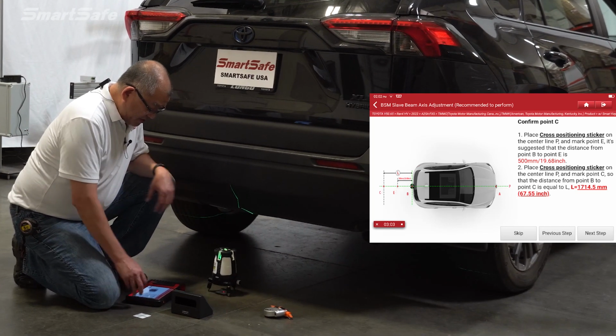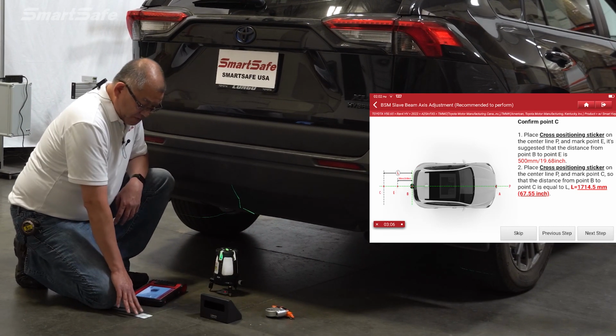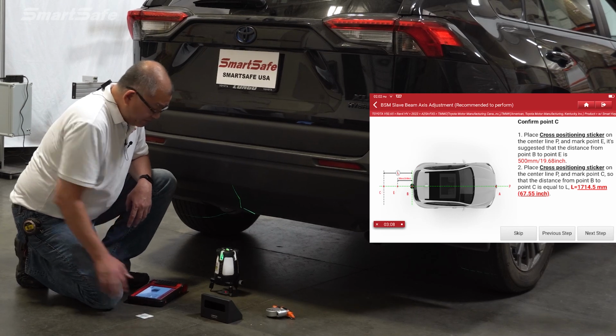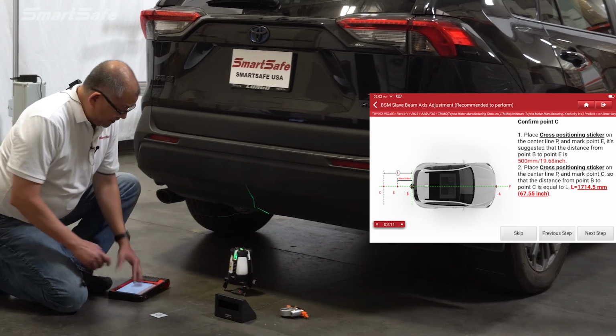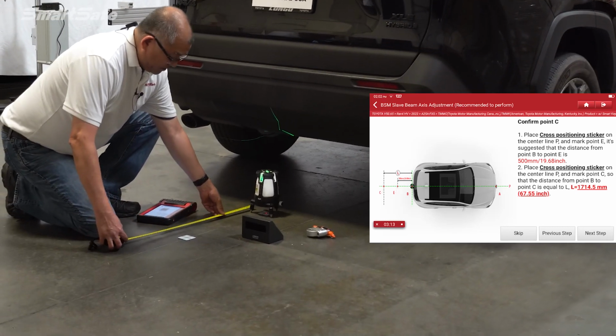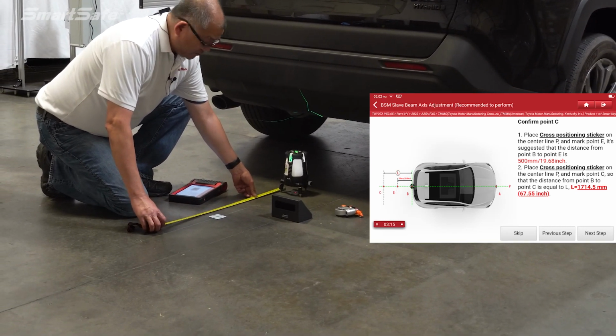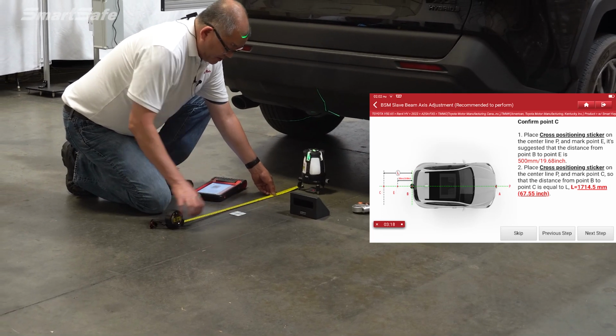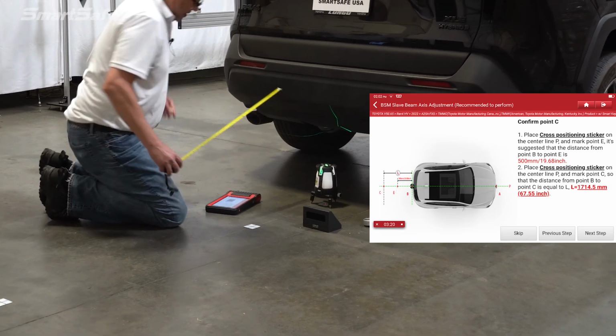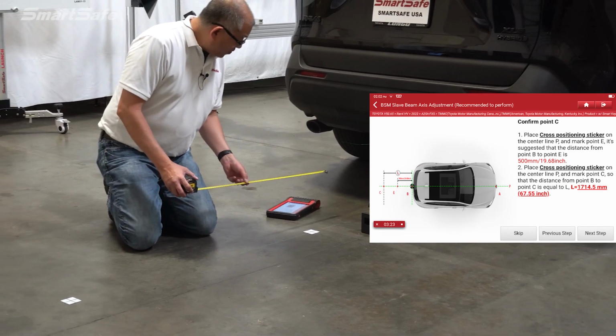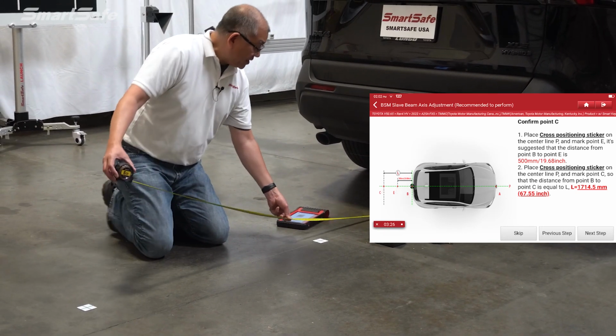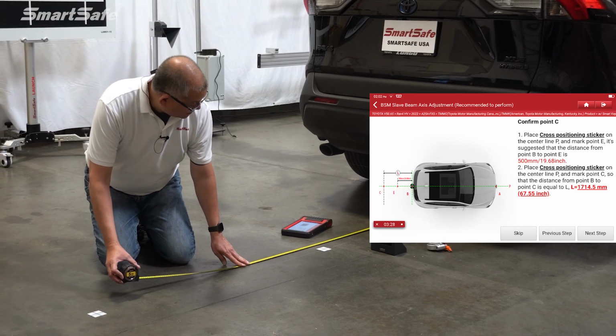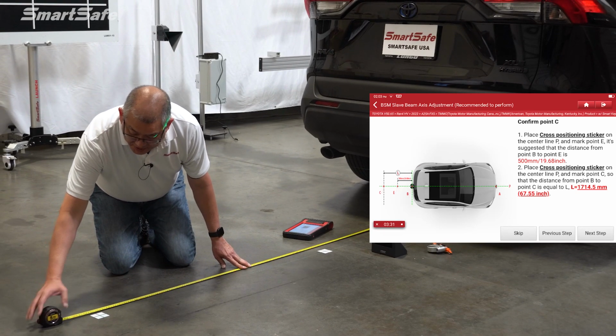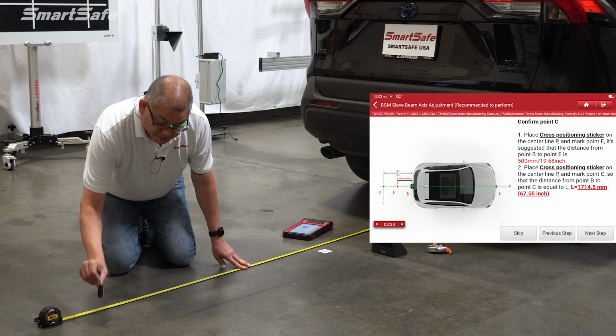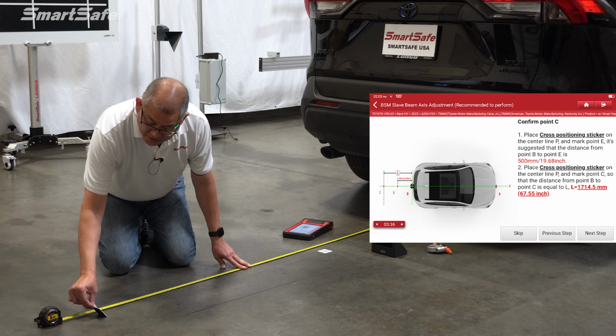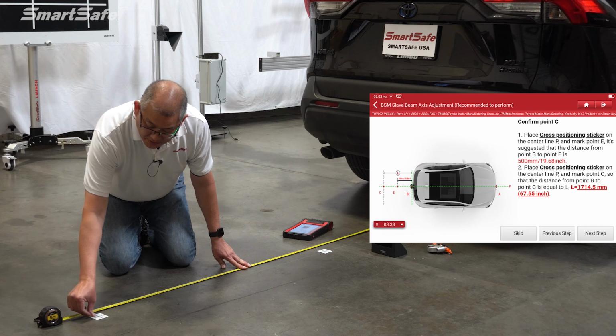So the first thing we need to do is mark 2 points. The first one is to mark at a distance of 500 millimeters from the center of the laser. So I've already gone ahead and done that. So this is our first point here at 500. And then we're going to do our next one at 67.55 inches or 1714 millimeters. So you can see that we've got that marked here already. And again, looking at the laser, we'll get our center and we'll place this target pad down.